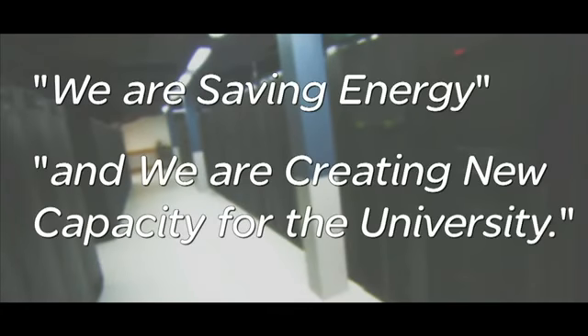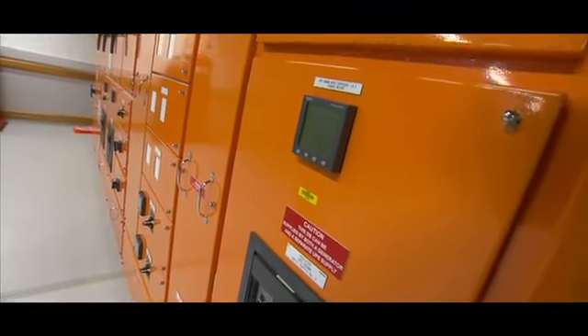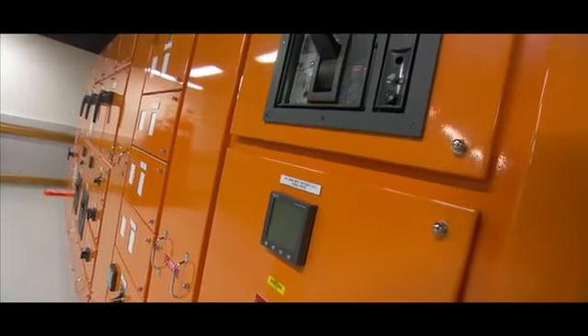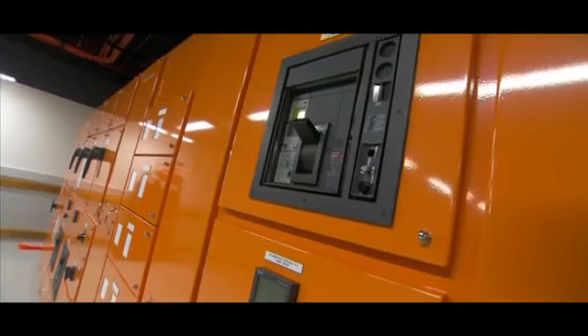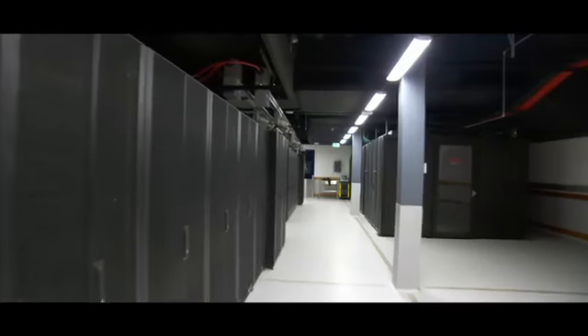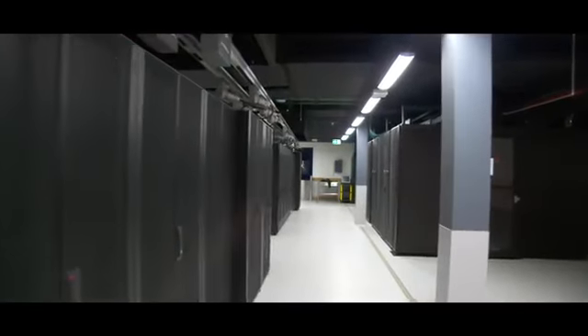The new cooling units cool air down to 22 or 23 degrees Celsius, not 14 or 15 degrees like in a traditional data centre. This not only makes a lot more sense in our climate, but it also results in significant energy savings. With a high-density data centre, we're creating capacity for future business operations. It's all about making the most of the system we already have, minimising power consumption, and making the best use of the site that we have invested in.